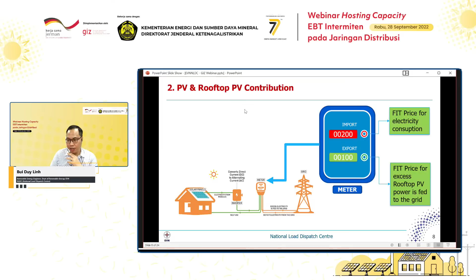Regarding the regulation for operation of rooftop PV, there are main features of the current regulation. The main regulation and standards addressing rooftop PV requirements is the guidance for technical requirements for rooftop PV inverters issued by NLDC, which applies to PV systems of more than 500 kilowatt peak. Remote monitoring and control capability of the inverter is not required. The condition for curtailment applies only in emergency cases, and this issue is mentioned in the power purchase agreement contract of the rooftop PV system.